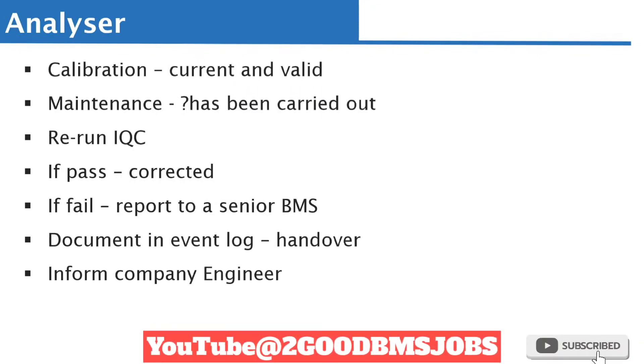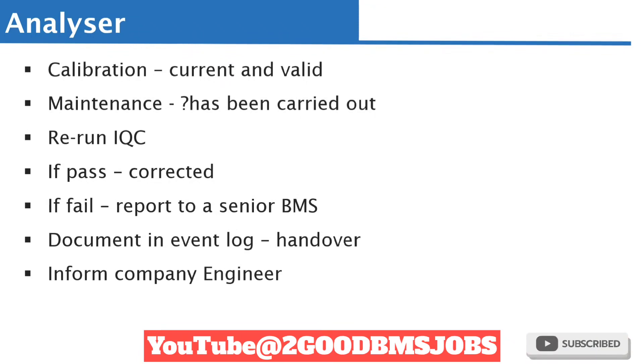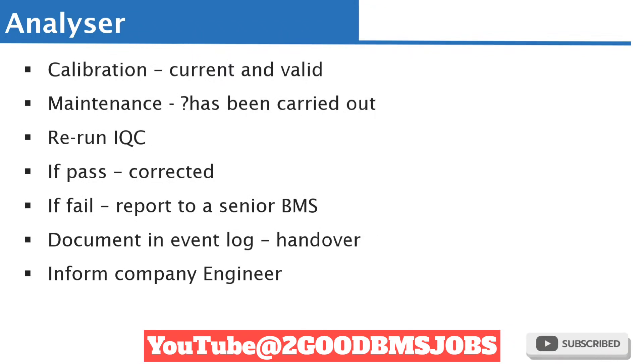The final factor is the analyzer itself. If you have investigated the control sample and the reagent and neither is the problem, you may need to consider it could be the analyzer. With the analyzer, check the calibration — is it correct and valid? Calibration plays a major role in how the analyzer measures and determines results. Also check whether maintenance has been properly carried out. No matter what happens during the investigation, you may need to perform maintenance and calibration where appropriate.